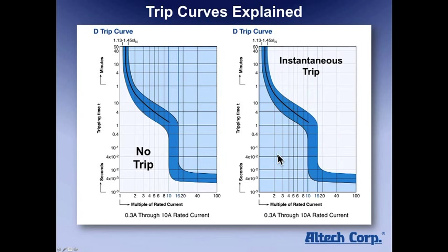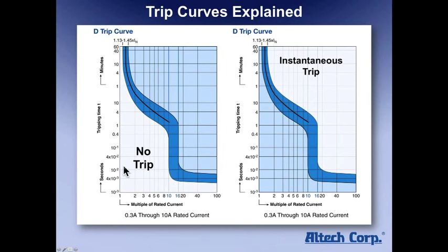That's why we have different trip zones. For example, you have a motor — if it's a 1 amp motor, it usually has an inrush current of 6 times rated current, so 6 amps. It's a real quick spike in the millisecond area, and it will not touch the curve, so it will not trip.